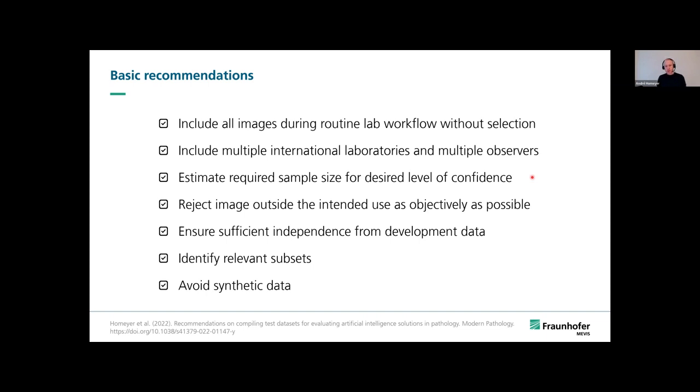The minimum sample size required for a desired level of confidence in the performance metric should be determined prior to data collection. This is not easy, but there are different statistical approaches for doing this for different sample statistics. It's also important to reject images outside the intended use as objectively as possible.